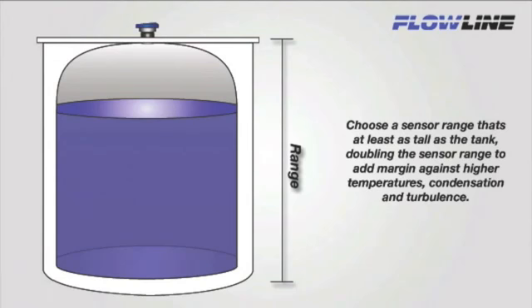Range is defined as the maximum measurement distance of the sensor. Most transmitters are offered in 2 to 3 different ranges. When selecting a sensor range, make sure the maximum range is not less than the tank height. Choose a sensor that has a range at least as tall as the tank; doubling the sensor range to add margin against higher temperatures, condensation, and turbulence is recommended.